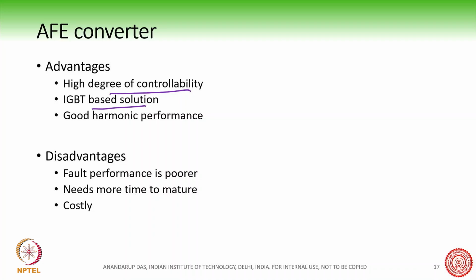It's an IGBT based solution, so you can turn it on and off. IGBT is very well established nowadays and has very good harmonic performance. You do not have to take additional precautionary measures, because you can switch the VSC in such a way that it draws sinusoidal current from the input side.